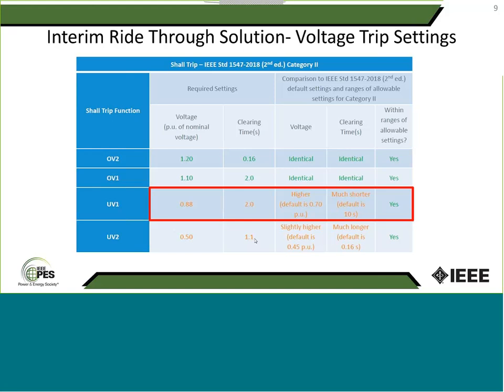There's no ride-through requirement for a fault on a distribution system, and there shouldn't be, because we want to make sure all the generators on that faulted circuit trip offline as fast as they can so that they don't impact the fault duty and arc flash and all the other things. The safety aspect is very critical on the distribution side as well. But the generator itself has no clue what's causing that under-voltage. The only thing it's doing is measuring voltage, at either the point of common coupling on the high side of the interconnection transformer, or in most cases the point of DER connection, which is the low side. Either the high or low side of the transformer is the voltage reference point, and the DER in general has no clue what's causing that under-voltage.